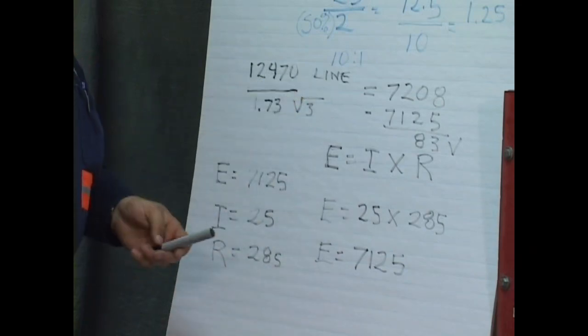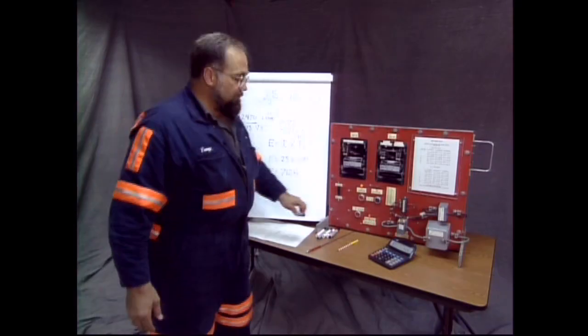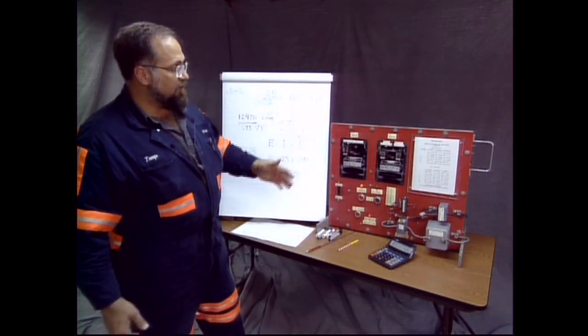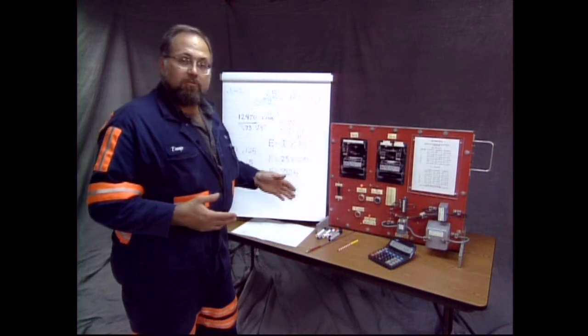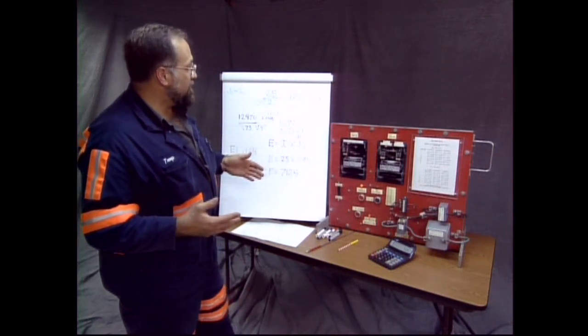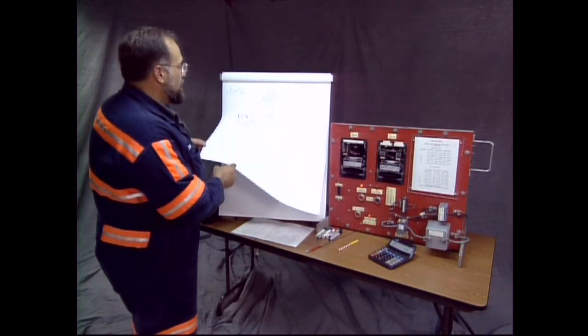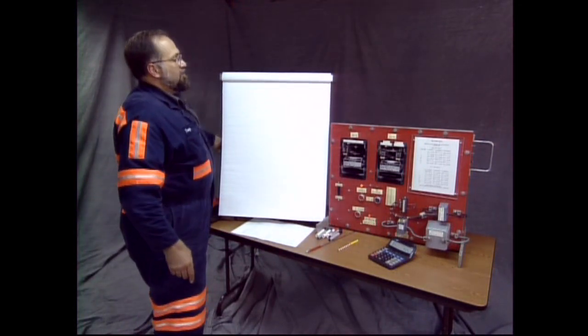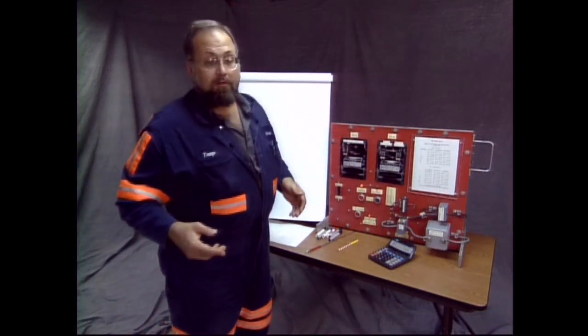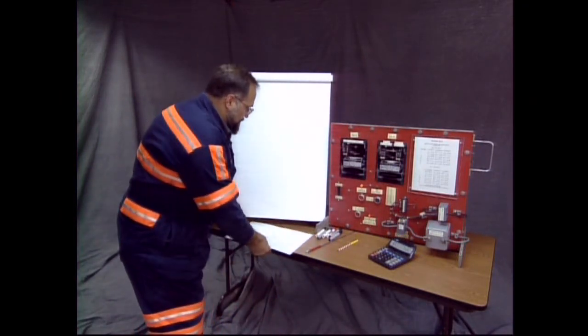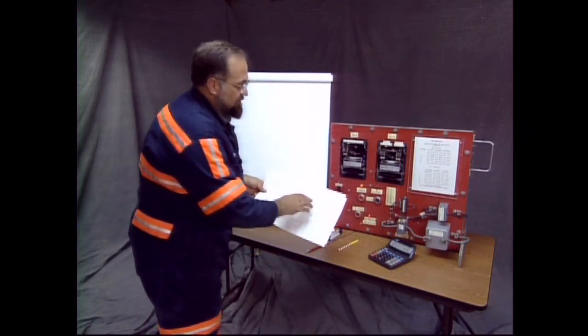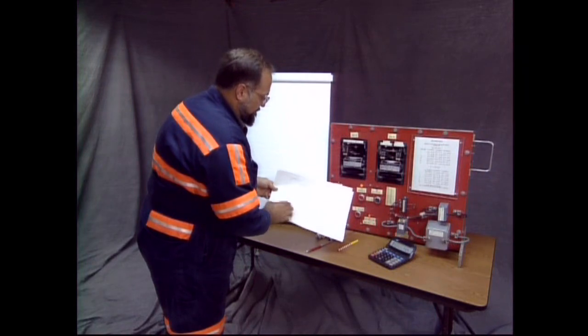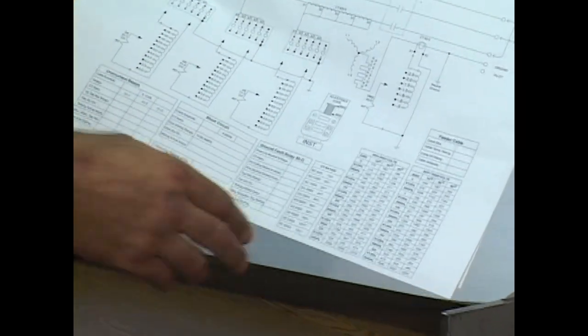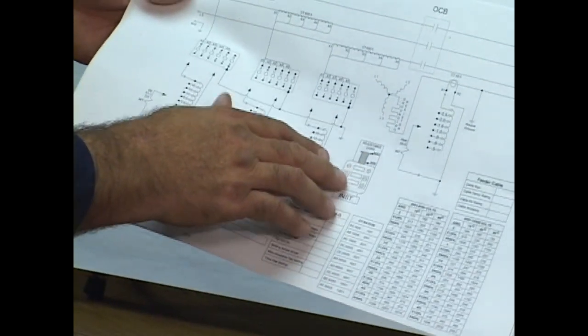Okay? That's all the math. All the math that terrifies everyone with this relay. That's it. You've set the relay. You've checked the ground resistor. You've found voltage external. And that's the extent of all the calculations that you might have to do. It's unlikely that you would have to set the whole relay for your test. You're going to draw a problem in a lotto fashion, and the state now uses this form, which has each CT ratios. That's just as we do, and they have the tap settings like those in the black, and they have an adjustable core relay just like this one that you would mark your various settings on.